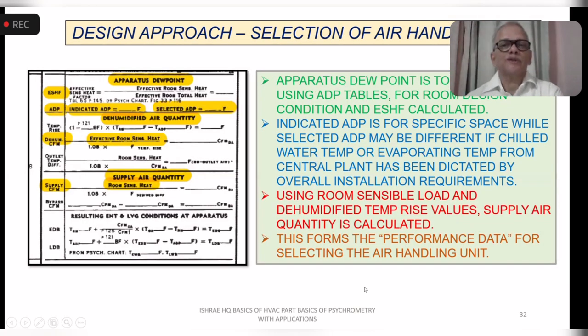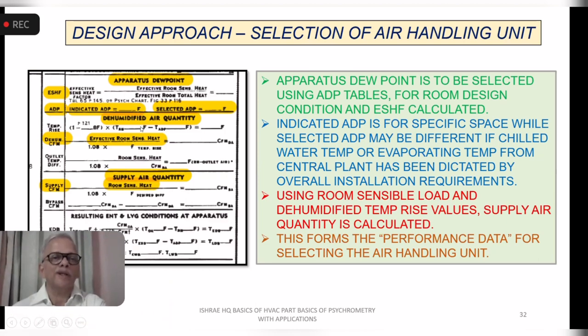Now comes the apparatus dew point. There is a part of that same chart or form which we saw, where you have these entries: apparatus dew point, indicated ADP and selected ADP. Then you get this dehumidified air quantity. The moment you use the word dehumidified, this is the cooled and dehumidified air. That is the quantity of air which you get from the dew point table. And then you have to use the air quantity, and that's where you will get the selection of the equipment.